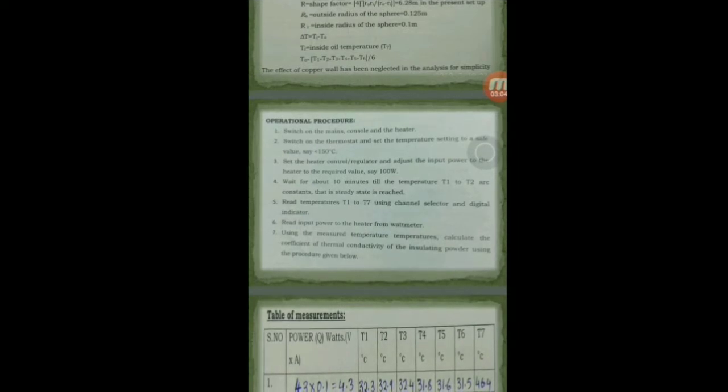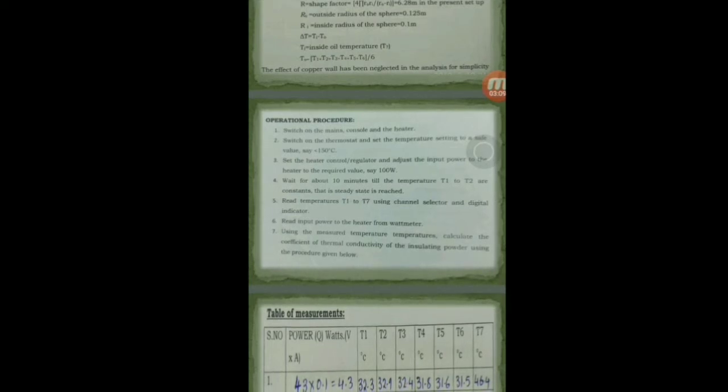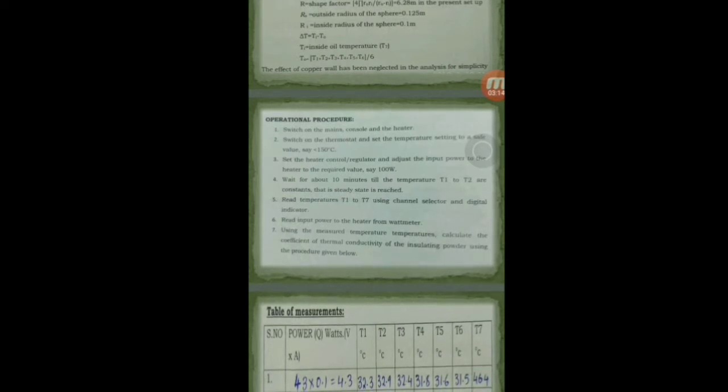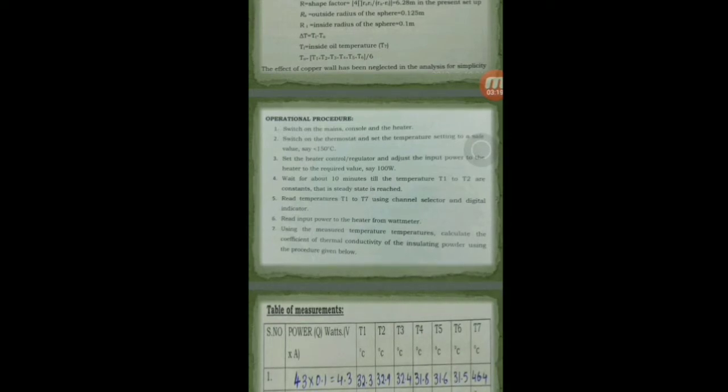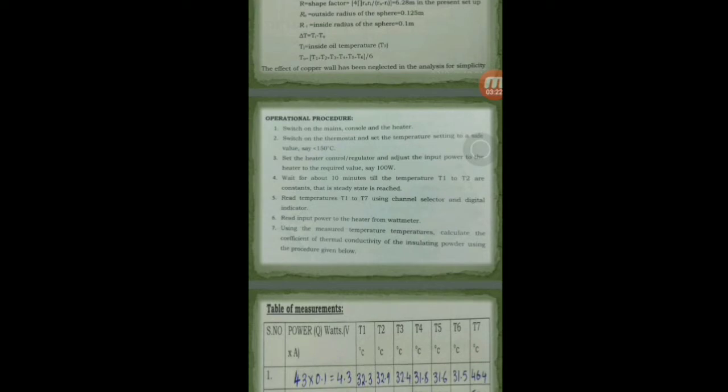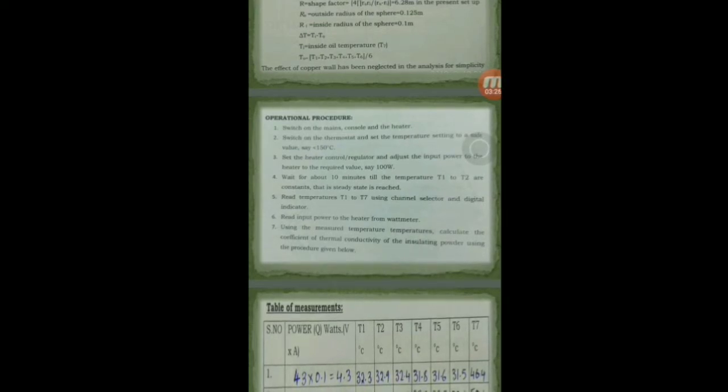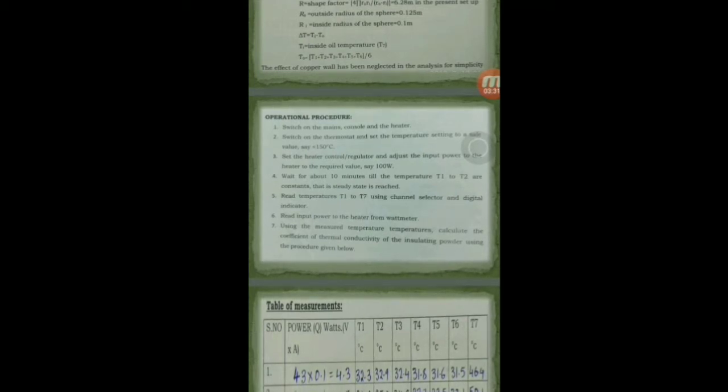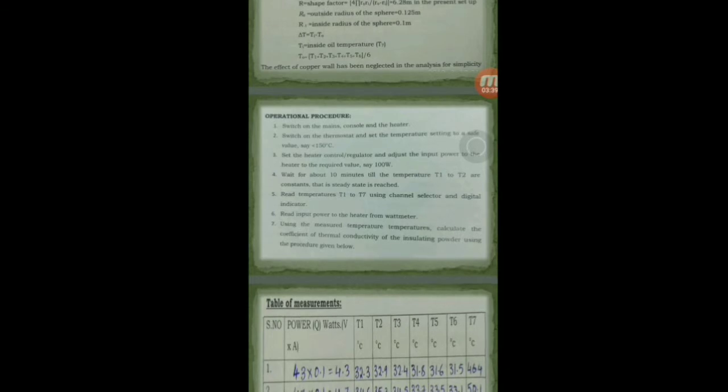The next step to be followed is the operational procedure. In the operational procedure, the first and foremost step is to switch on the mains, then the console and the heater. Then, switch on the thermostat and set the temperature to the required value, maybe less than 150 degrees centigrade. It should never exceed 150 degrees centigrade. Then, set the heater control or the thermostat and set the input power to the heater, maybe like 100 watts. Then, wait for a few minutes, maybe 10 minutes, till the temperatures are constant, that is, the steady state is obtained.